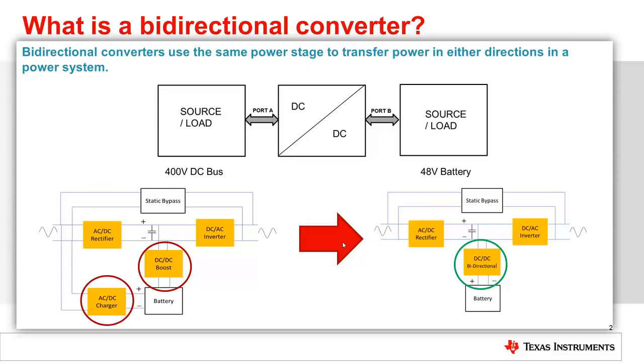An alternate approach would be to use a single bidirectional DC-DC converter, which is capable of taking power from the 400 volt DC bus and charging the battery, and when the AC mains fails, can take power back from the battery and feed it into the 400 volt DC bus.